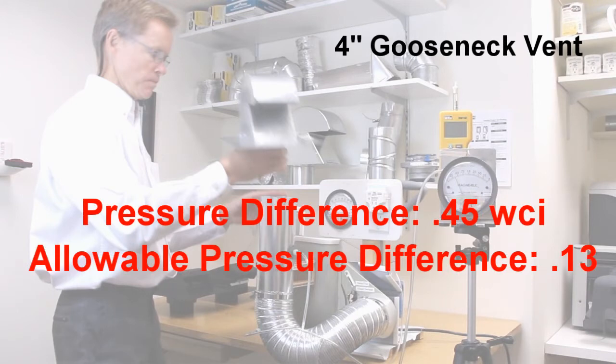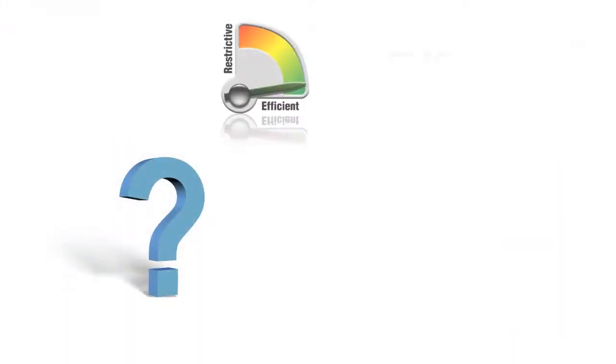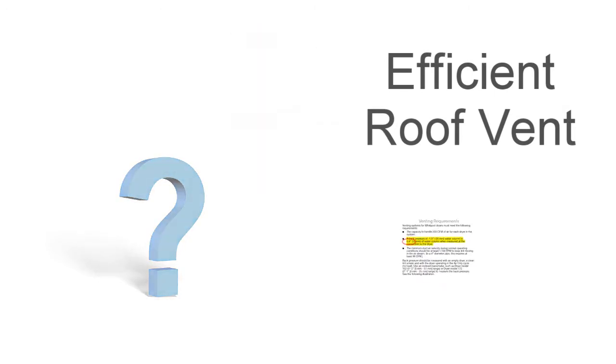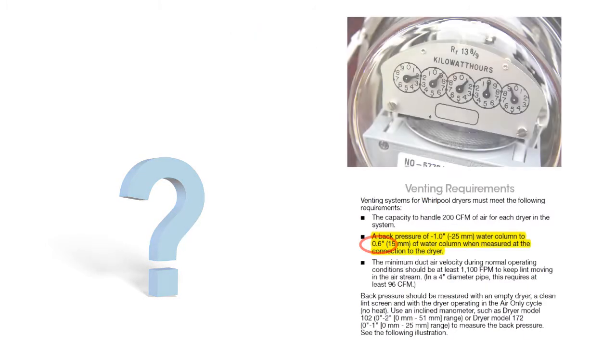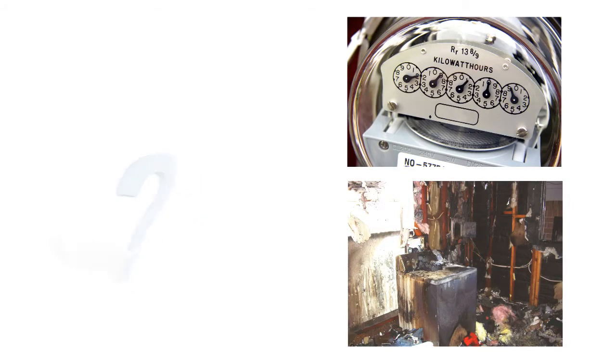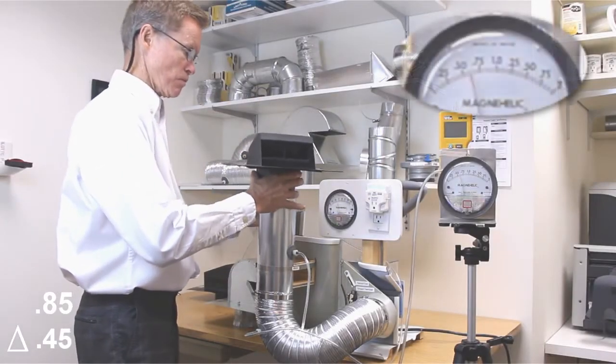In our first test, the four-inch gooseneck provided more than three times the allowable pressure level, and it's here we start to see why an efficient roof vent becomes attractive in not only meeting the appliance manufacturer's minimum requirements, but saving energy and minimizing any fire risk. Let's continue with the test.